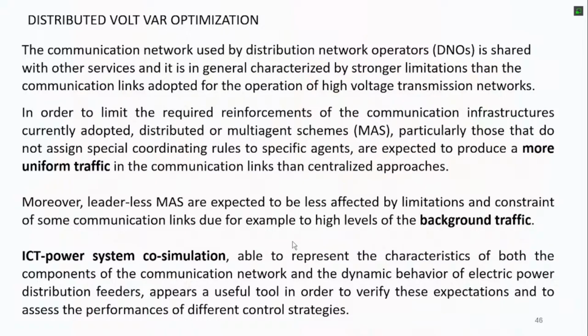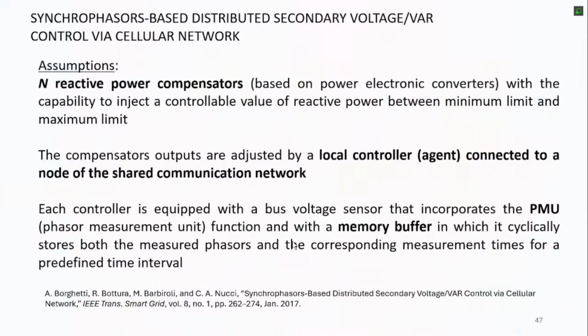And we have already installed the co-simulation, and that was the same that we have used also for the other aspect. So what is the idea behind this study? It is to use controllers that have the capability to calculate, to measure, to estimate not only the magnitude of the voltage, so the RMS value, the root mean square value of the voltage at the bus, but also the angle. So they are equipped with a phasor measurement unit, PMU, function.